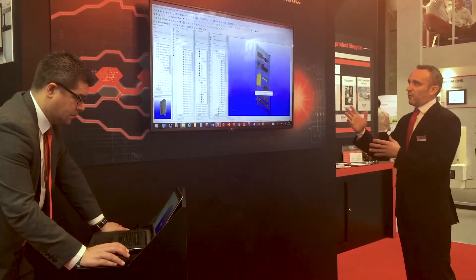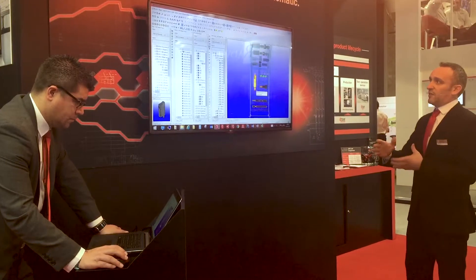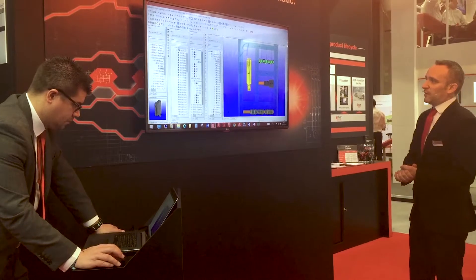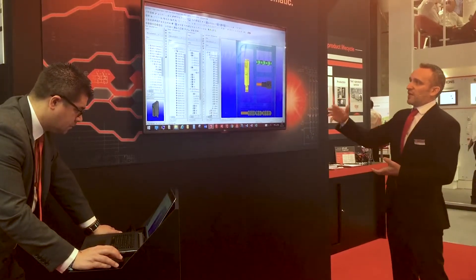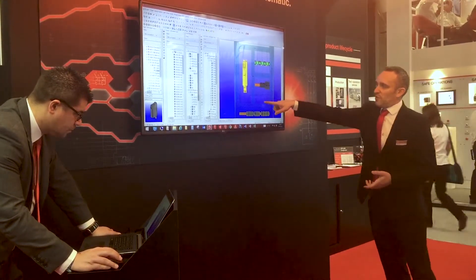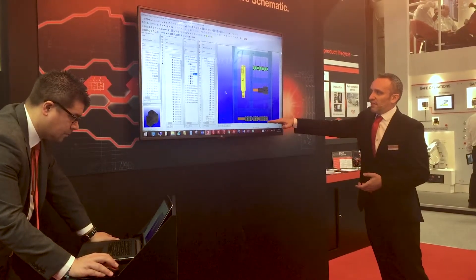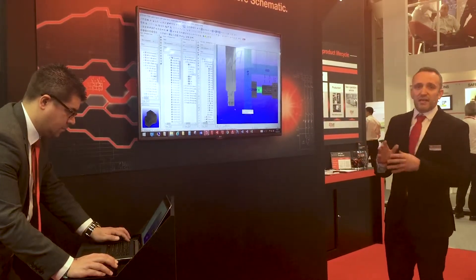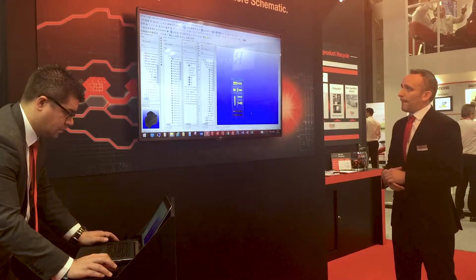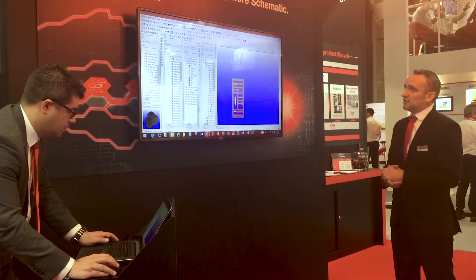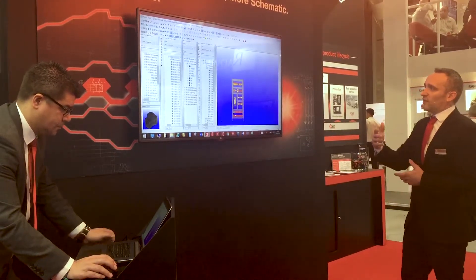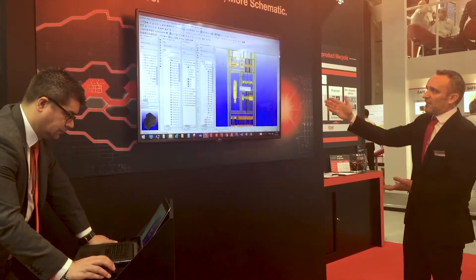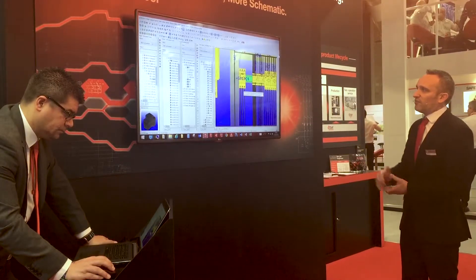We can come back to the panel layout now and look at some of the other benefits of this 3D — things like automatic wire routing. John should be able to re-route this panel for us now quickly. This will update all the wire lengths, where you can see we've got some breaks where we changed the height of that trunking. We'll then be able to route that and get accurate wire lengths. It's taking all the wiring information and getting accurate wire lengths, generating the information very, very quickly.